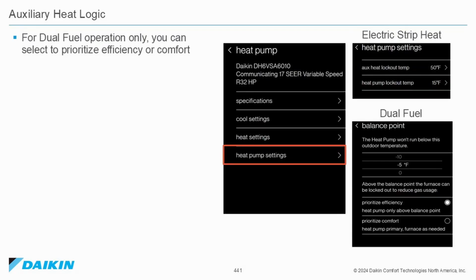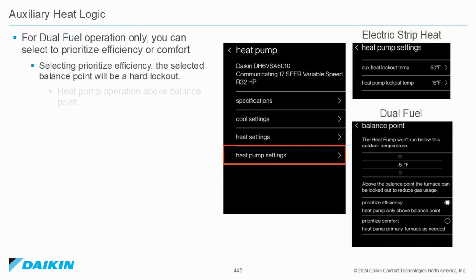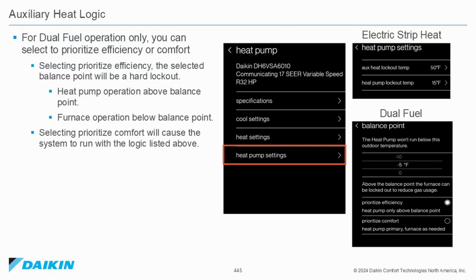Auxiliary heat logic. For dual fuel operation only, you can select to prioritize efficiency or comfort. Selecting prioritize efficiency, the selected balance point will be a hard lockout. This will give you heat pump operation above the balance point, furnace operation below the balance point. Selecting prioritize comfort will cause the system to run with the logic listed above.